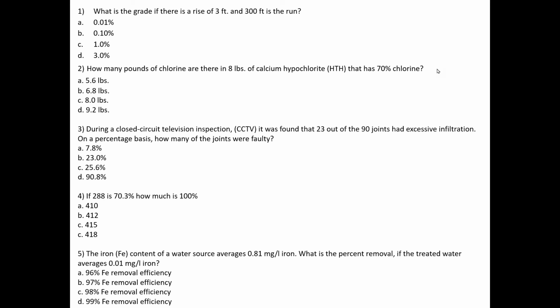So you can eliminate D and C completely. You can wipe them out, just by knowing what calcium hypochlorite is. Now, normally, the most that I've ever seen with calcium hypochlorite is 65%. That's been the answer, but this has it as 70. I'm not going to fight that. Okay, so yeah, it's 0.70 times 8. But you can look at these and eliminate D and C. Because if it was C, that means it's 100% pure. If it's D, it's more than 100% pure.